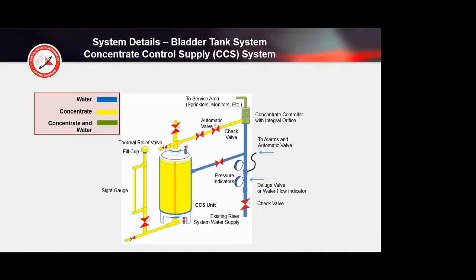Once the fire is detected, it sends a signal to the fire panel, kicks off the alarms, whatever notification goes into place, and then comes back and opens up the deluge valve to allow the water to start to flow. As the water starts to flow, it goes into the outside of the bladder tank. So this is a steel tank. Inside is a bladder. Inside the bladder is the 100% F-500 EA concentrate. As the water is going up, it's coming through a ratio controller, which is your proportioning device. The water's coming here. It's squeezing that rubber bladder.